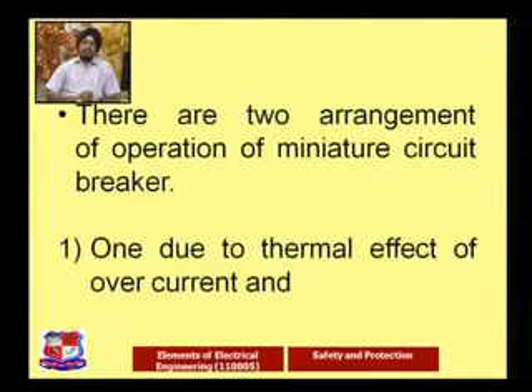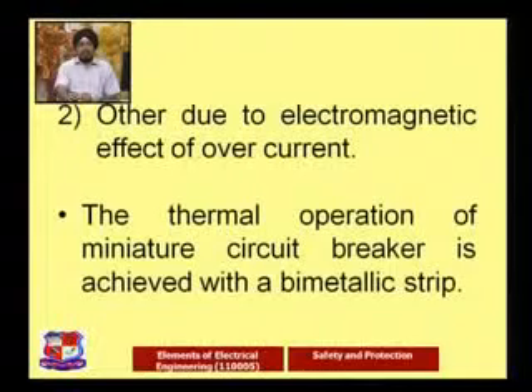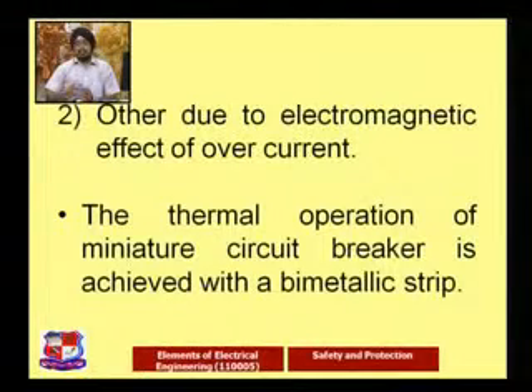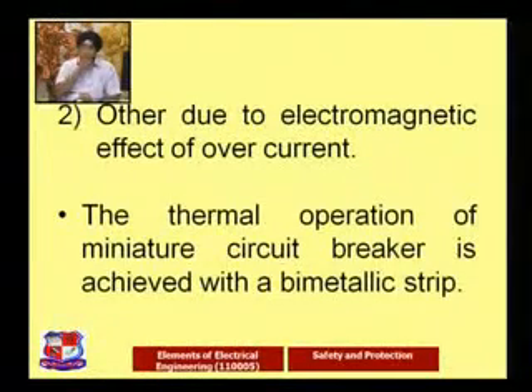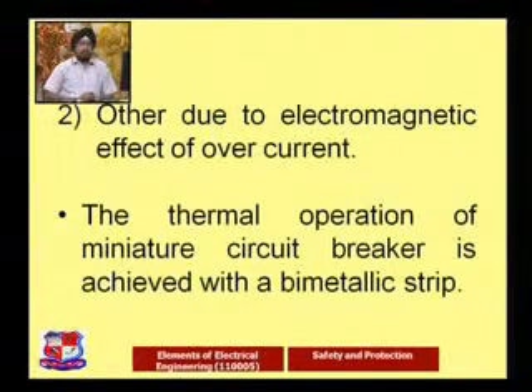The first one, we want to protect the circuit with the help of thermal effect due to the overcurrent. Similarly, electromagnetic effects are there. So thermal effects are there, electromagnetic effects are there. So we have to overcome that, and that's where, instead of the fuse, MCBs have the upper hand. They have the advantage. So for the thermal protection, as we know, the bimetallic strips are there. With the help of those strips, we are able to achieve the thermal protection.